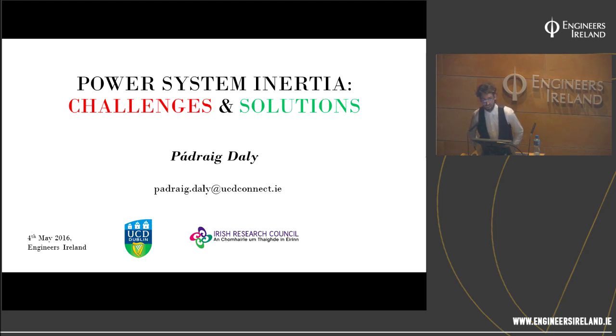Yes, in short, you can't just have synchronous condensers, because they'll only help with your rate of change of frequency decline. You can't form the nadir and bring the frequency back to nominal with the synchronous condenser. Synchronous condensers are great. I love synchronous condensers. If I get enough time, I'll do plenty of research on them, because they give you fault current, dynamic and steady state voltage control, and a small bit of inertia. Okay, it's not big.